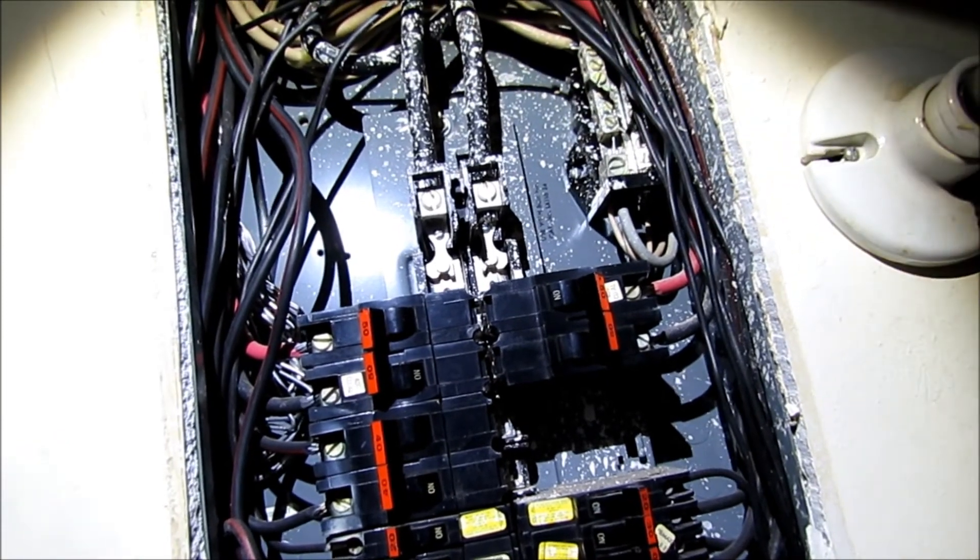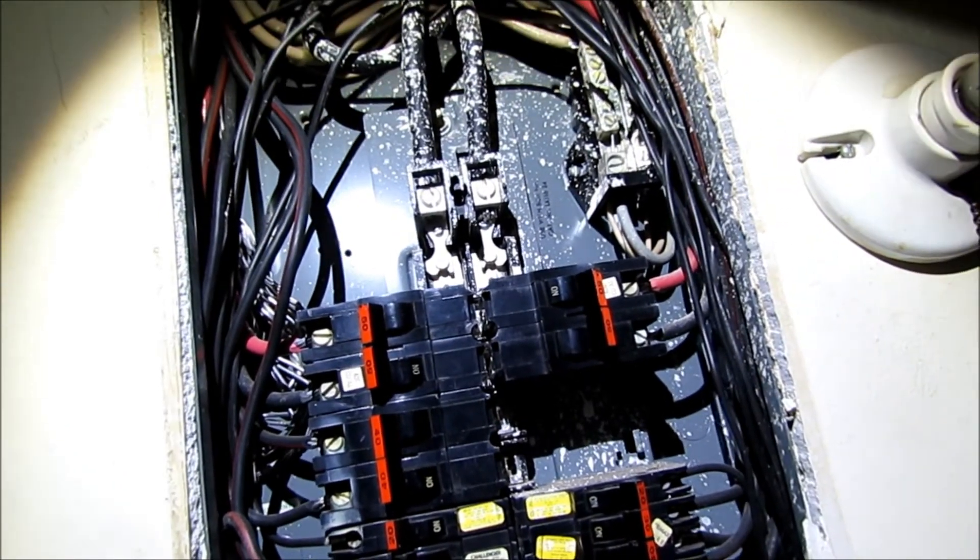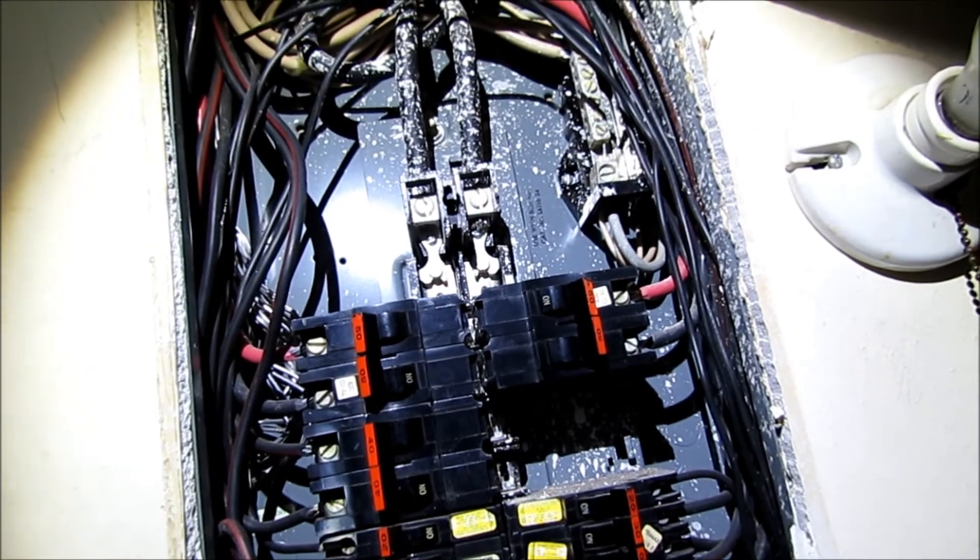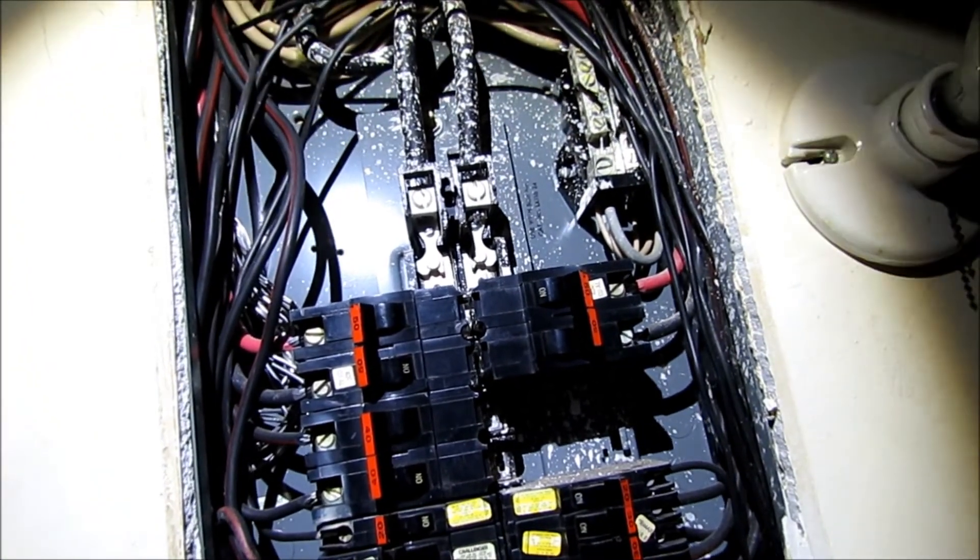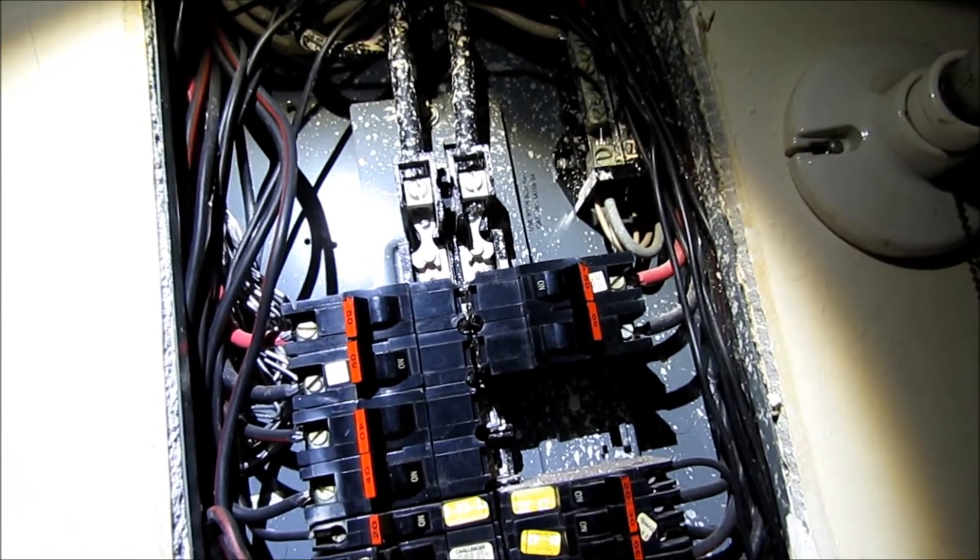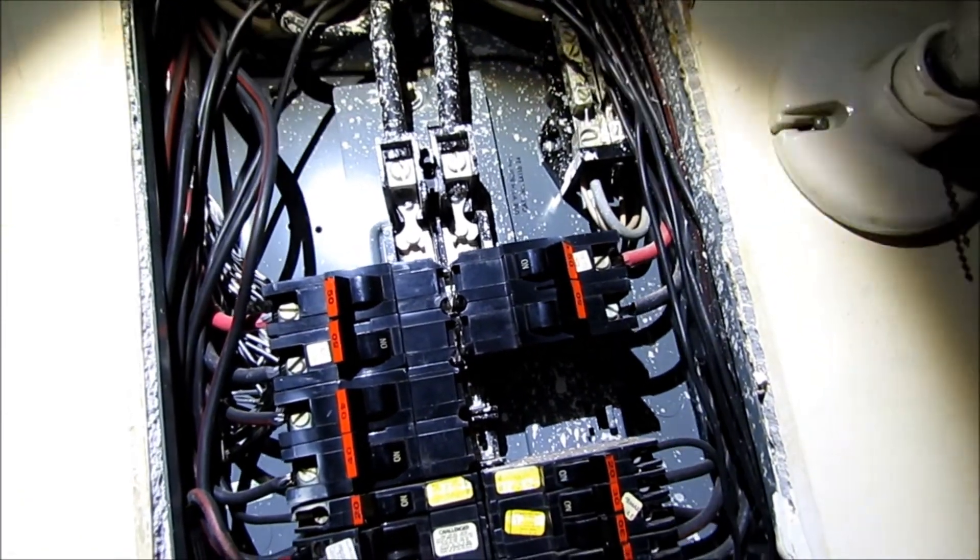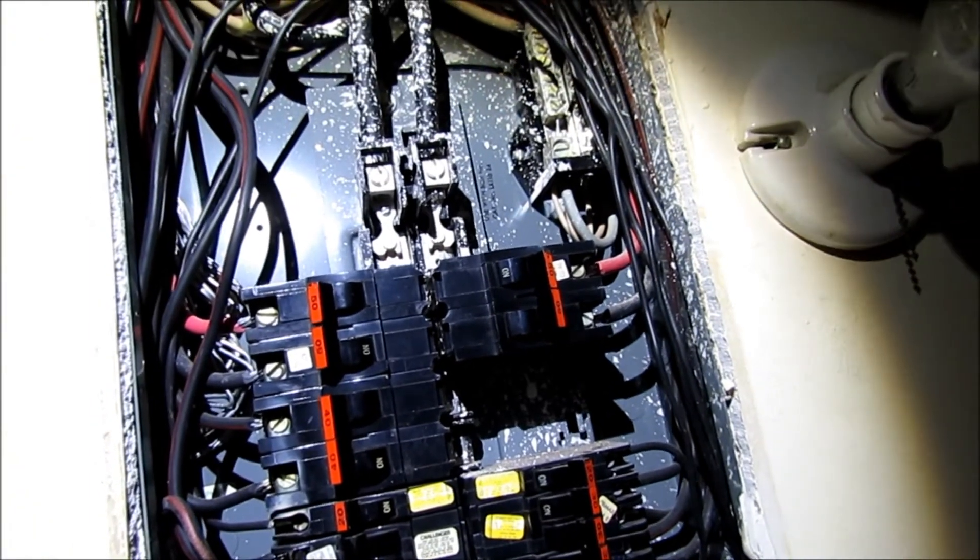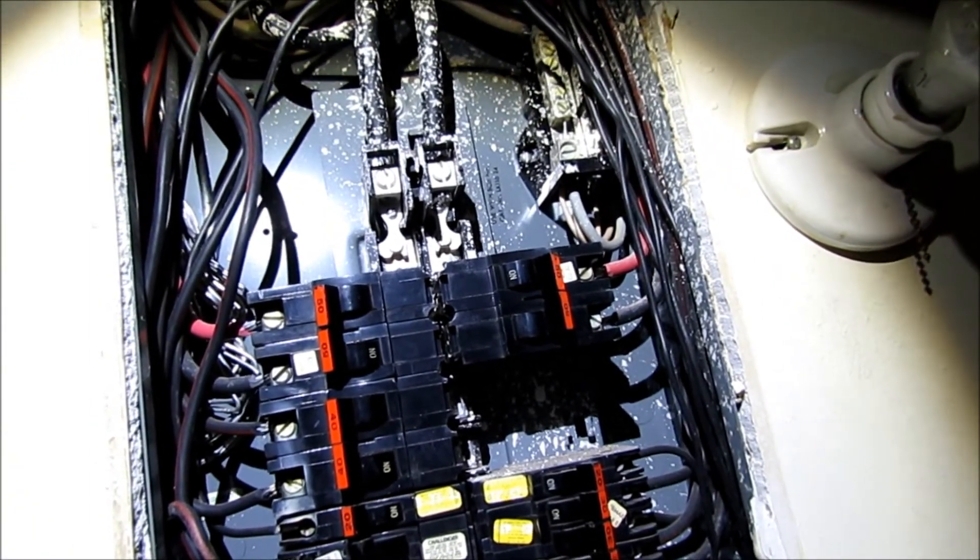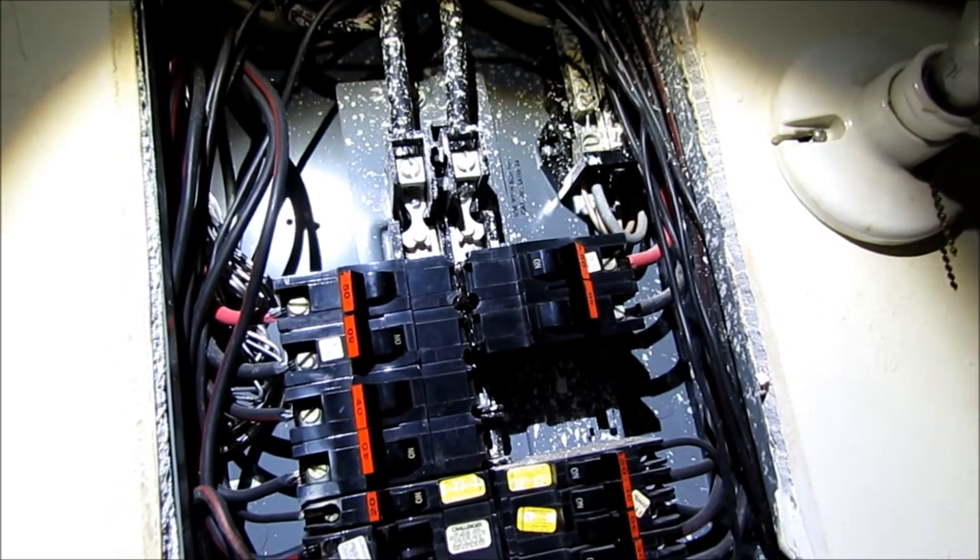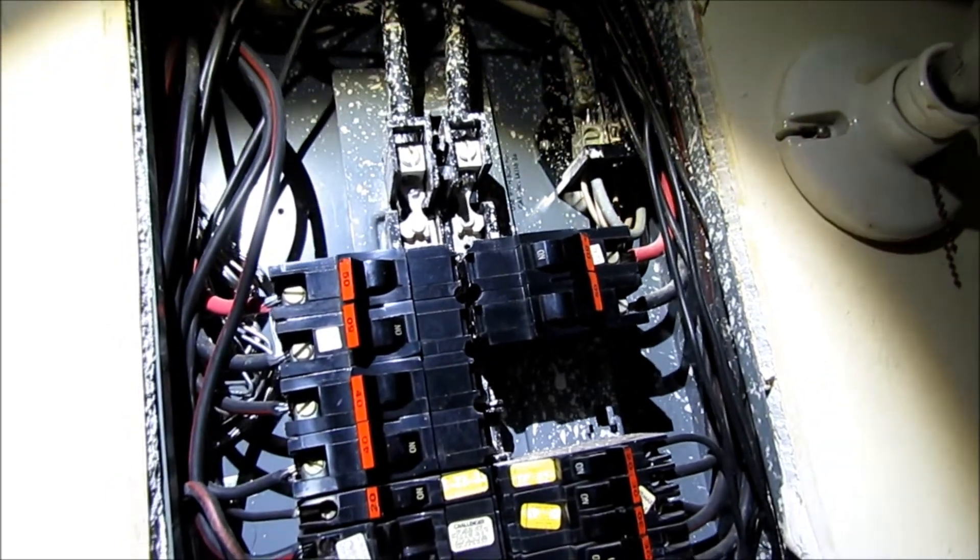And so just know that there are some service panels out there that have been reported as being defective and they can pose somewhat of a fire hazard to your home. And I know of one case where a guy was not able to get insurance as a result of one of these Stab-Lok panels until he had it corrected.